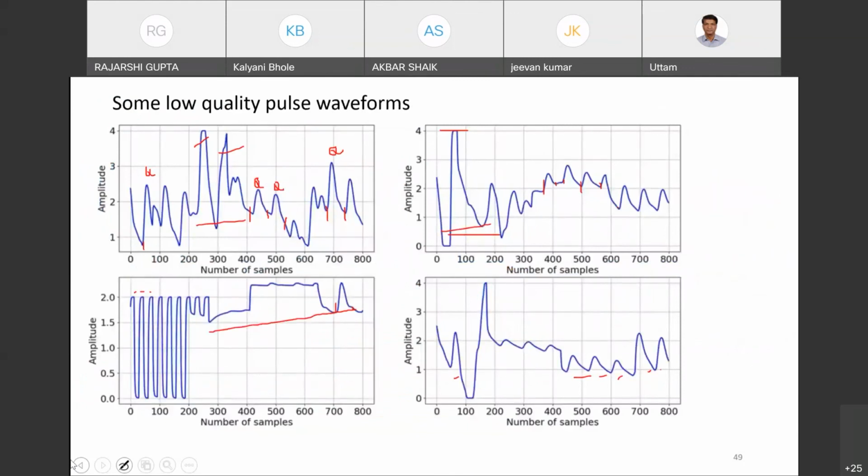If we can devise something that measures the signal quality beat by beat, and instead of discarding the data, also calculates the blood pressure from each of the beats and provides some confidence value. For example, when a beat appears to be partly corrupted, I will say that whatever blood pressure value I am providing is 60% accurate. So for all of these beats, I will be providing some measurement.